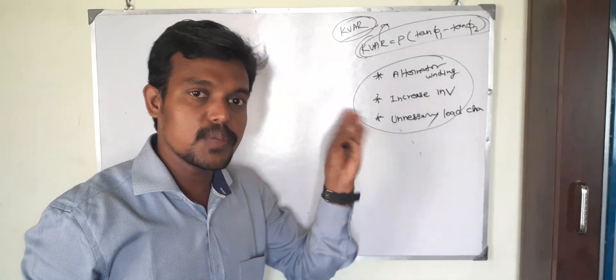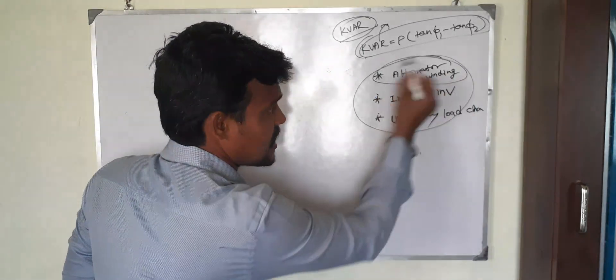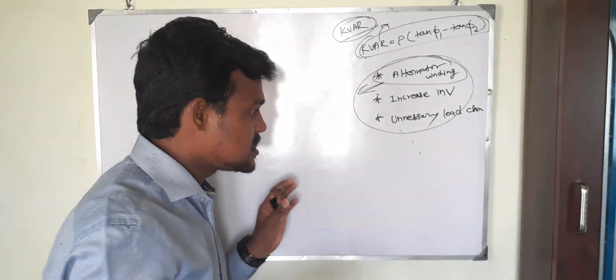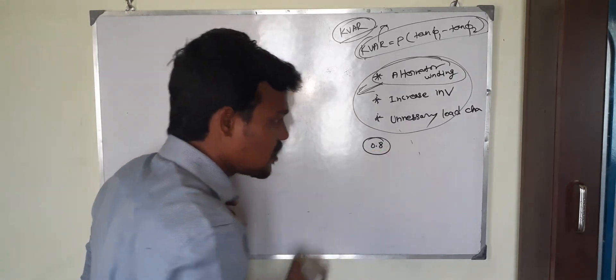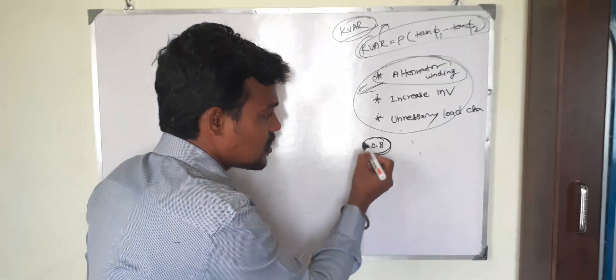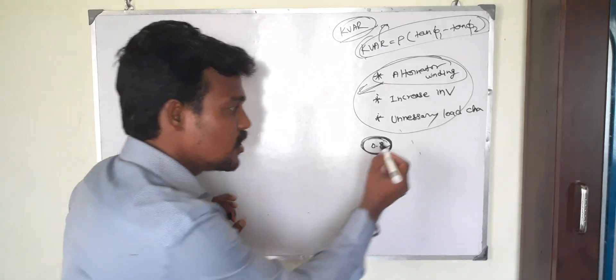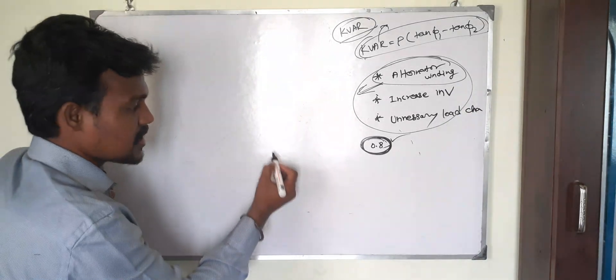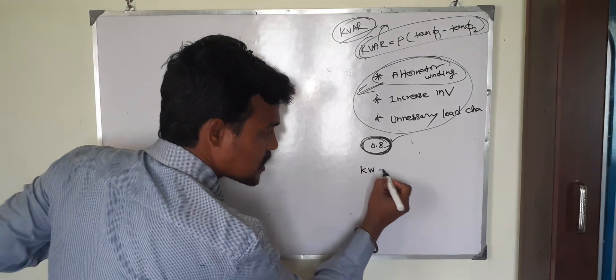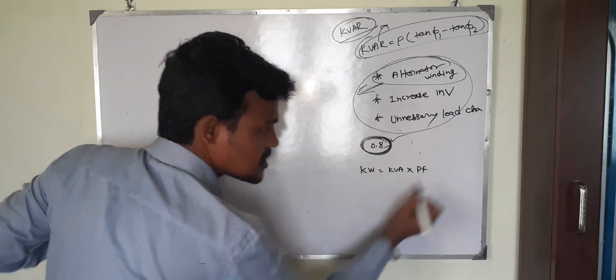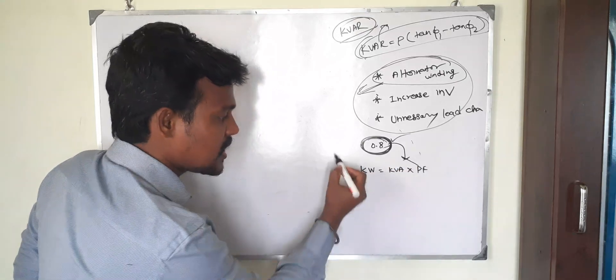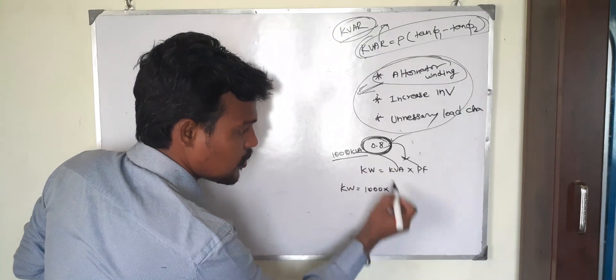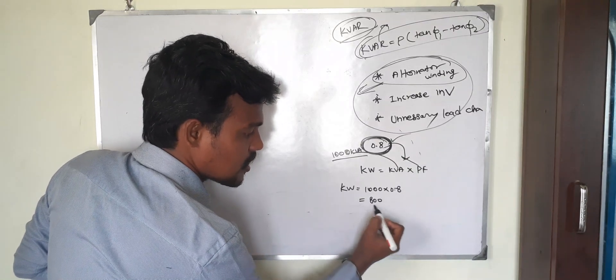I will explain why the alternator winding gets damaged. If you look at the nameplate of your DG, the power factor listed is 0.8. This means the DG is always designed at 0.8 power factor. The full load of that DG is designed with respect to 0.8 power factor. The formula is: kilowatts = kVA × power factor.